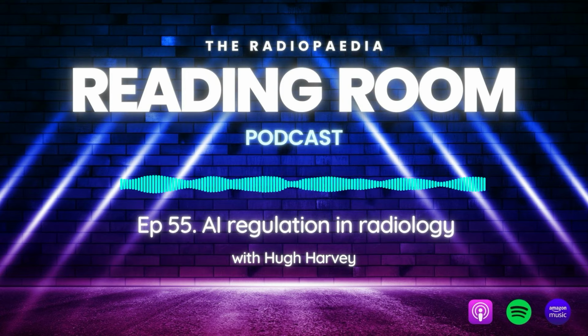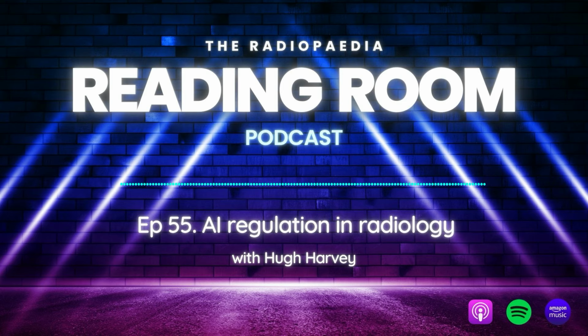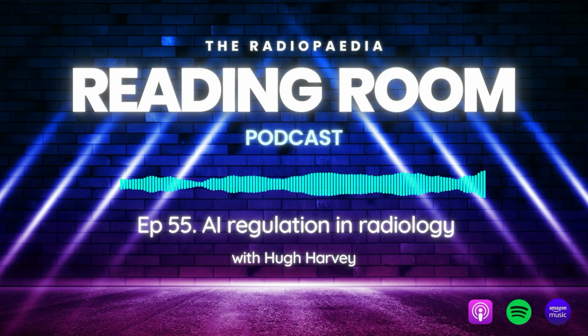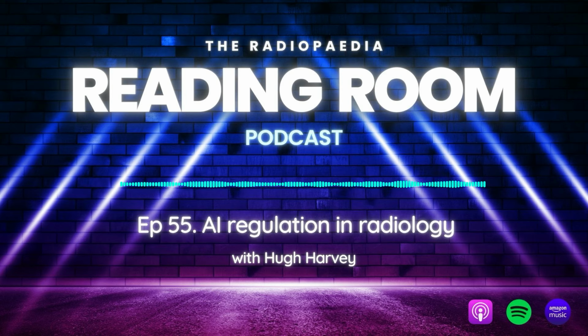What's the difference? There are differences in the amount of evidence you have to present, differences in the amount of technical documentation you have to present, and differences in the post-market surveillance you have to conduct afterwards. So obviously, a class 3 device requires more pre-market evidence and more post-market evidence than a lower-risk class 2. By and large, the vast majority of radiology AI systems that you're seeing injected into PACS are class 2A, unless they're dealing with cancers, in which case they're likely to be class 2B.